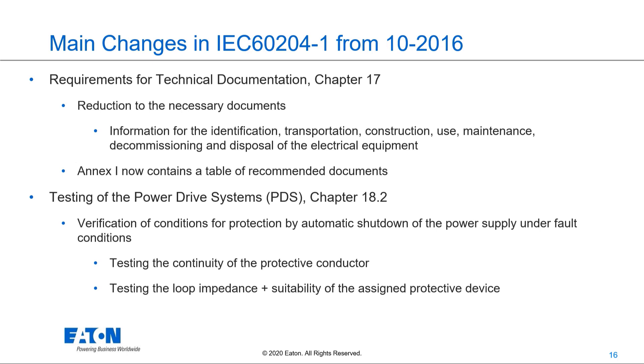In Chapter 18.2 there is a new chapter on testing of the power drive system. Verification of conditions for protection by automatic shutdown of the power supply under fault conditions must be made by testing the continuity of the protection conductor, by testing the loop impedance, and by verifying the suitability of the assigned protective device.